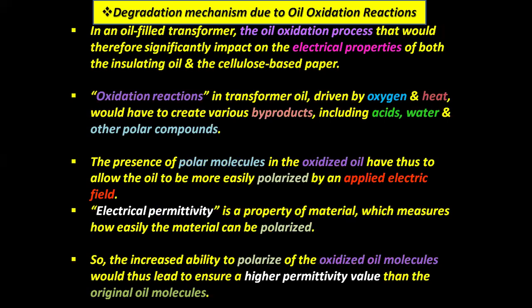Now, the degradation mechanism due to oil oxidation reactions. In an oil-filled transformer, the oil oxidation process significantly impacts the electrical properties of both the insulating oil as well as the cellulose-based paper insulation. Oxidation reactions in transformer oil, driven by oxygen and heat, create various byproducts, including acids, water, and other polar compounds. The presence of polar molecules in the oxidized oil allows the oil to be more easily polarized by an applied electric field.